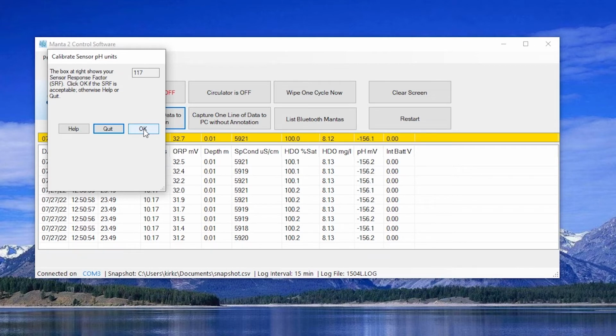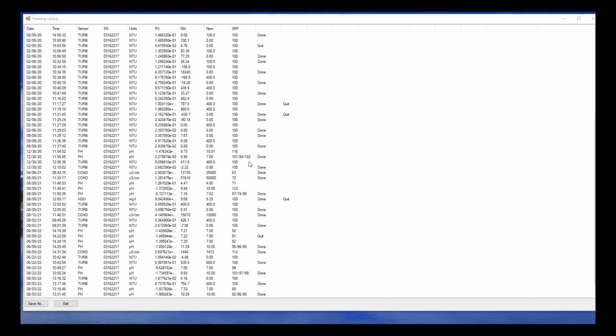If your SRF is significantly outside that range, it likely means your sensor needs cleaning, your reference electrolyte needs to be changed, your buffers are faulty, or you mistyped your buffer value. The pH SRF has three numbers. The first indicates the success of your first buffer. The second indicates the success of your second buffer. The third indicates your overall success compared to the calibration of a typical pH sensor.